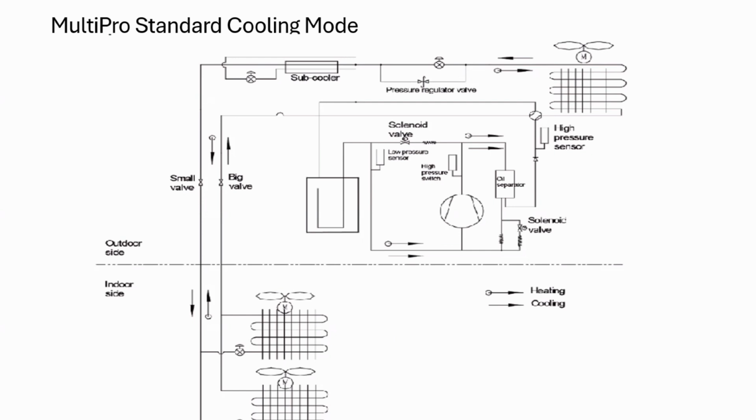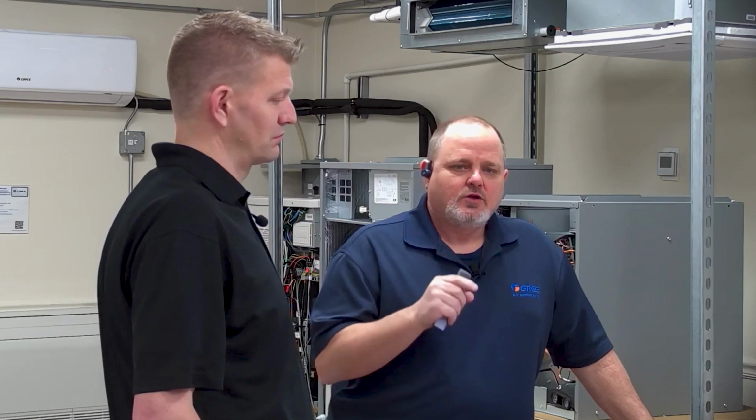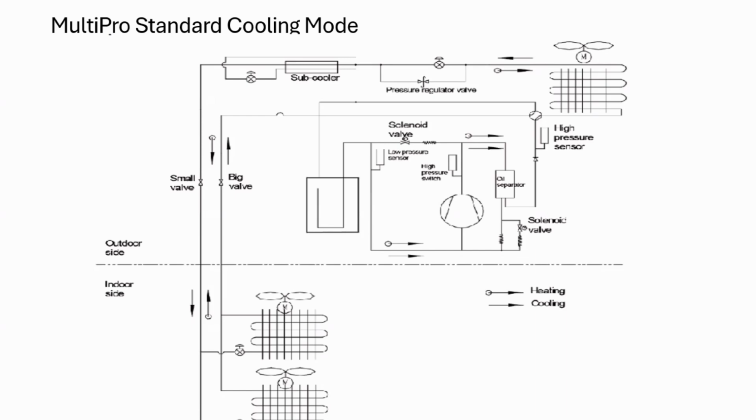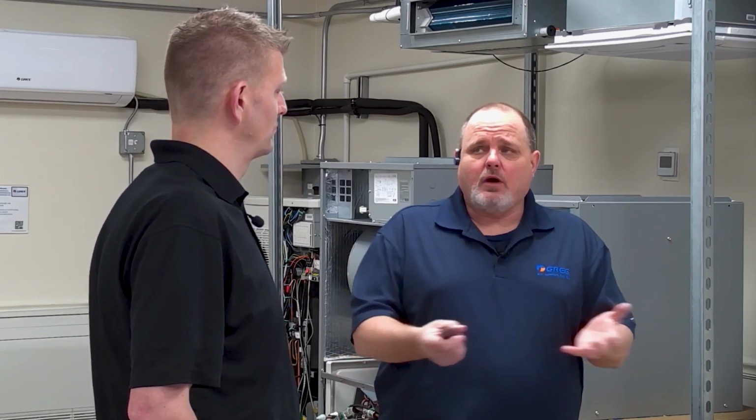But every time you go there and you reset the error code, whatever the compressor error code may be, you reset that error code and you start up the system and you bring on all 4 indoor units. And you monitor it for a half hour, an hour, or whatever, and the system's working and it's not going down on fault. And you're thinking to yourself, well, maybe it was just a fluke. Maybe it was some scenario that caused that thing to weird out and shut down. But we all know that that's probably less likely.